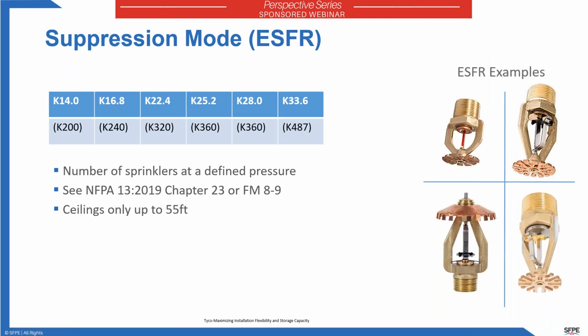Suppression mode sprinklers, ESFRs, early suppression fast response, were developed in the late 80s with the K14 sprinkler. The K25 sprinkler launched in the late 90s. Through the 2000s, we've added quite a few more K factors: 16.8, 22.4, and over the last year, K28, and then very recently, JCI launched a new ESFR 34 sprinkler, or K33.6. The ESFRs essentially offer the fire protection schemes with the highest ceiling-only allowances.